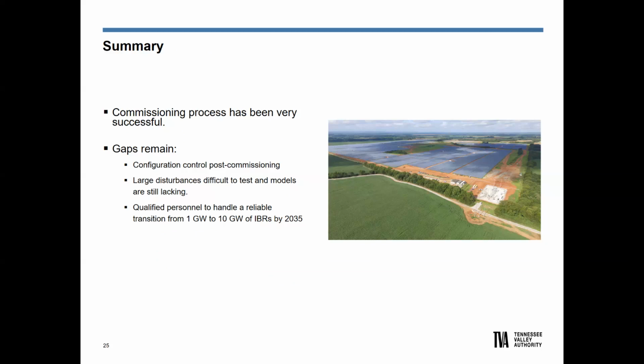We also, during the testing and burn-in period, are not going to perturb the system with a large disturbance. How to match that real-time performance with EMT testing or dynamic model testing is still pretty lacking to figure out going forward. And then we also need qualified personnel. Someone else talked about this too: how to handle that reliable transition from roughly 700-800 megawatts now, less than a gigawatt, to 10 gigawatts of IBRs by the 2035 aspirational goal. So that's it for TVA.